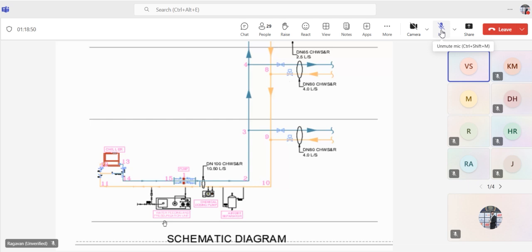Sometimes, if it goes beyond your allocated limit, you have to go for a diversity factor. When you add up all the flow rates based on the selection, you will get one final value. I'm pretty sure it will not match your design value; there will be some percentage difference. If you are doing a chiller, which means not district cooling, then it's fine. You will change the flow rate of the chiller and the pump. Finally, you have to do the selection, not at the beginning. That's the reason the consultant will say that when you do the pump selection, you have to submit this pump head calculation based on the selection of each and every individual unit.